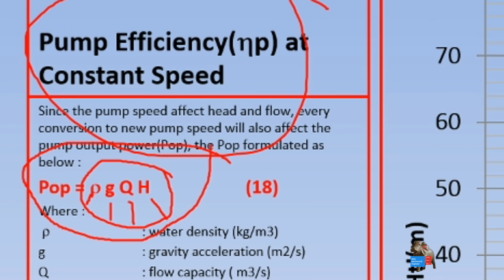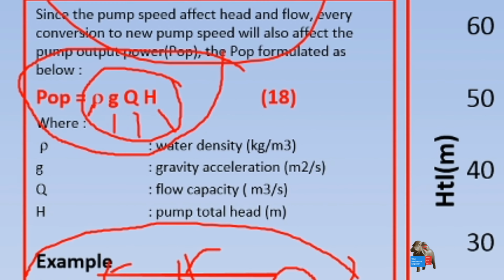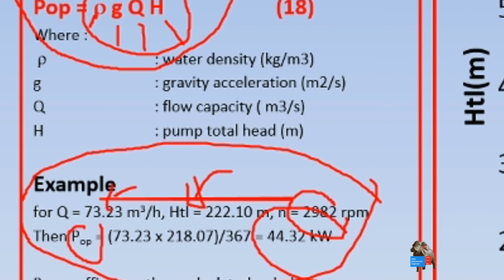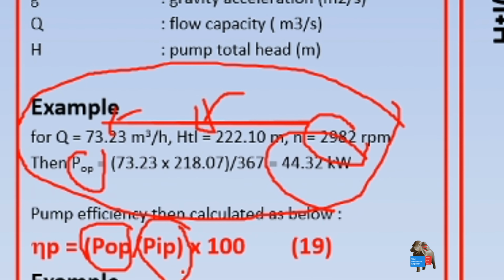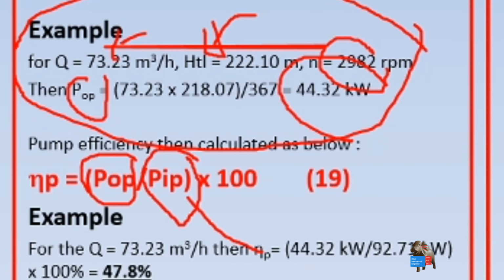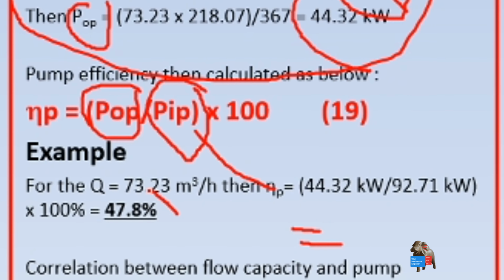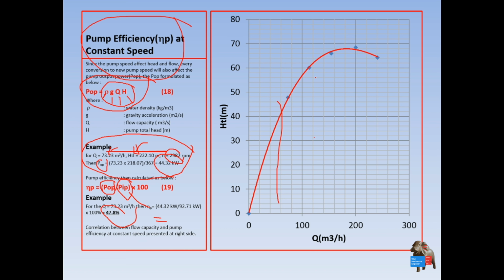The power input to the pump, as I explained before, will be the power output of the motor. Then if we divide the power output of the pump by the power input of the pump, which is considered the power output of the motor, you have the efficiency. So you have the values at least at 2, 3, 4, 5 points, and from these points you generate the pump efficiency. As you can see, the pump efficiency is not linear. At some point it will drop. Why it drops is another topic, considering eddy current and so on, and the limitation of the pump itself.